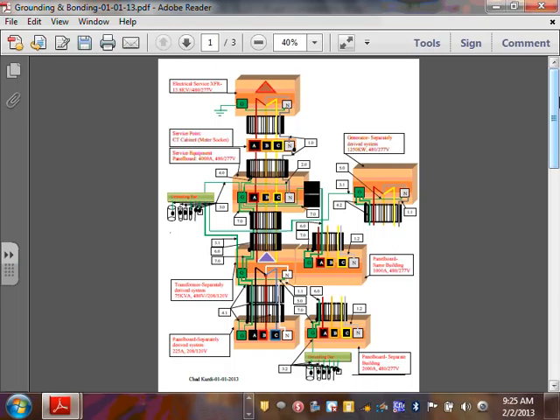Okay, and again, I will zoom into this one. I'm going to go right in here and just walk you through. If you start from the top here, this is your utility transformer coming over here. Typically, we're talking about a three-phase system, right? This is a three-phase, big power system. So if you look at the top here, you have 13.8 kV, I believe, primary delta, typically coming into 480/277. And typically, the system that comes to you is a Y grounded system. So the utilities will take your neutral here and ground it. They have a ground rod at their transformer.